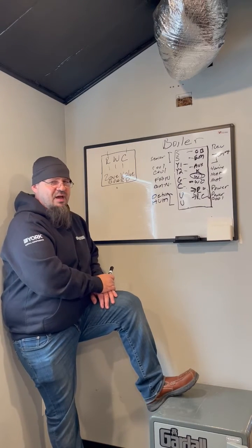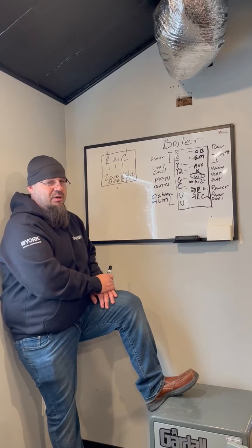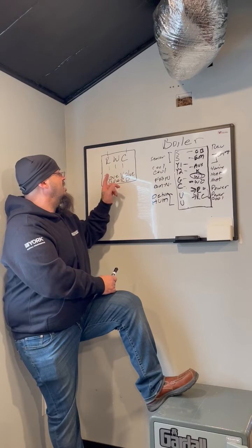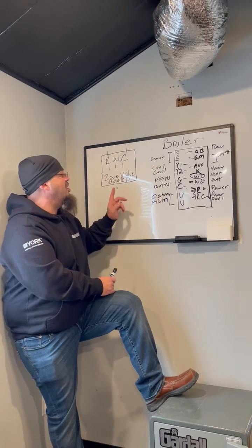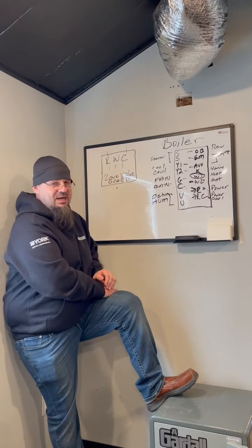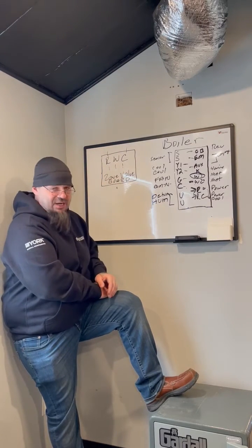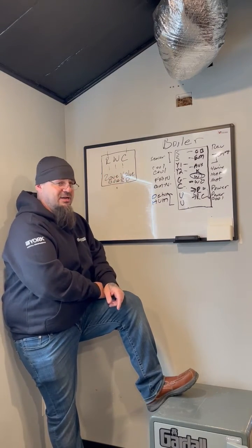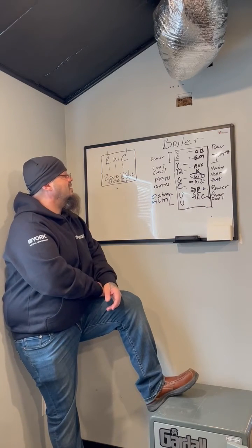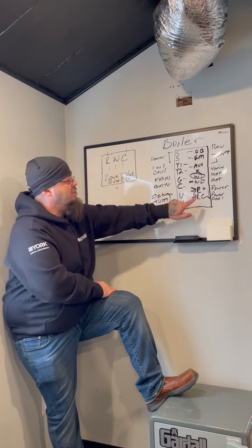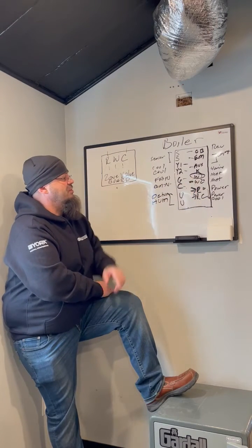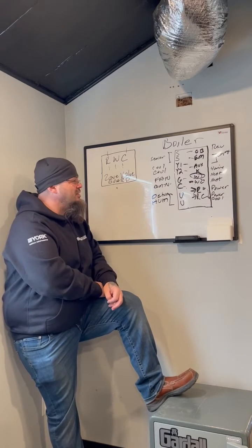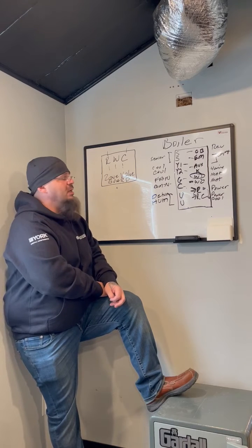So if you have a zone valve multi-zone system in your house on a boiler, and you really want a Nest or a power stealing thermostat, you can look into this and see. You look at your zone valve board, if you happen to have one, and you pull the cover off and take a look inside there, and if you see this RWC, then you definitely are in business. So you need RWC in the board, and you need a 3 wire going up to the thermostat, and if you have those things, then you can get that done by hooking these 3 terminals to these 3 terminals, respectively, R, C, and W. Again, you're flirting with danger with this one.